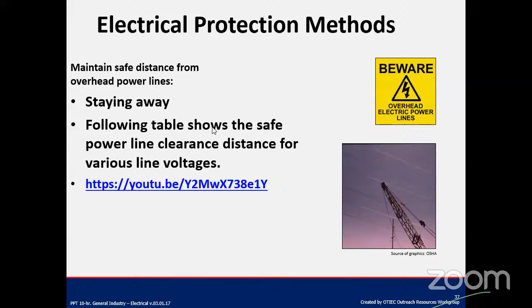How much distance should we maintain from overhead power lines? See, here a small table is given. Up to 50 kV, 10 feet safe distance required. 50 to 200 kV, 15 feet. 200 to 350 kV, 20 feet. 350 to 500 kV, all for alternating current. This is the minimum clearance distance we must maintain.